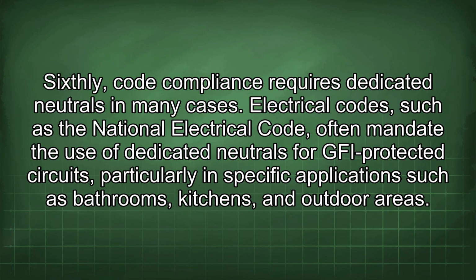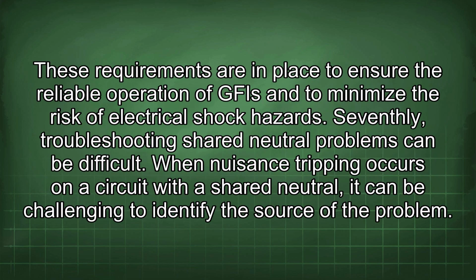Sixthly, code compliance requires dedicated neutrals in many cases. Electrical codes, such as the National Electrical Code, often mandate the use of dedicated neutrals for GFI protected circuits, particularly in specific applications such as bathrooms, kitchens, and outdoor areas. These requirements are in place to ensure the reliable operation of GFIs and to minimize the risk of electrical shock hazards. Seventhly, troubleshooting shared neutral problems can be difficult.